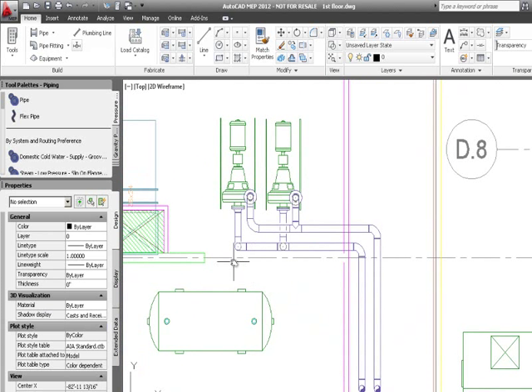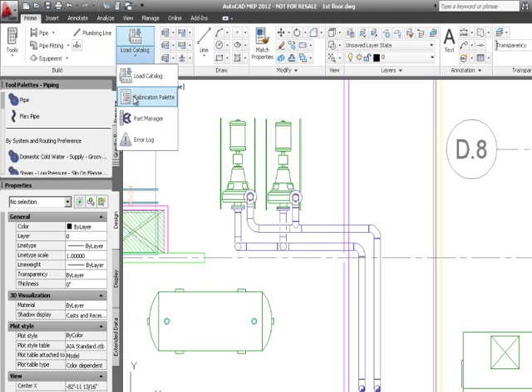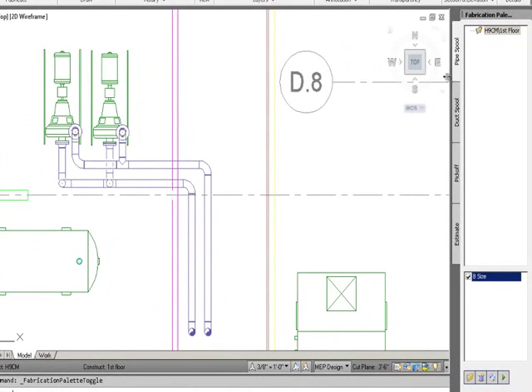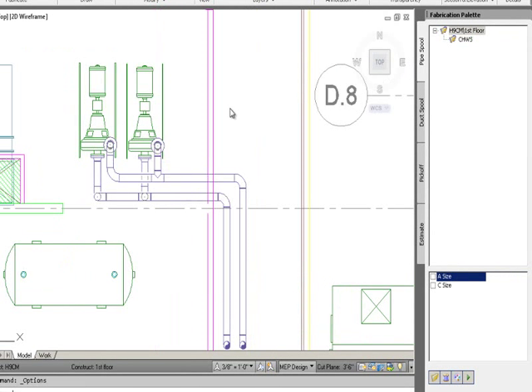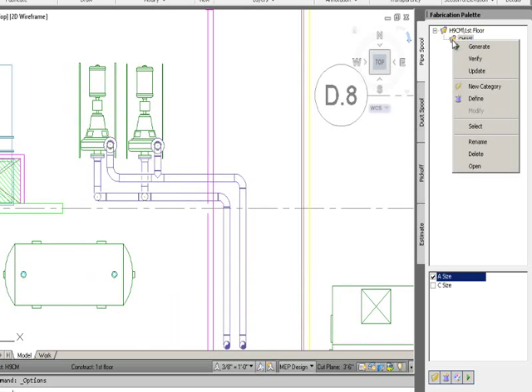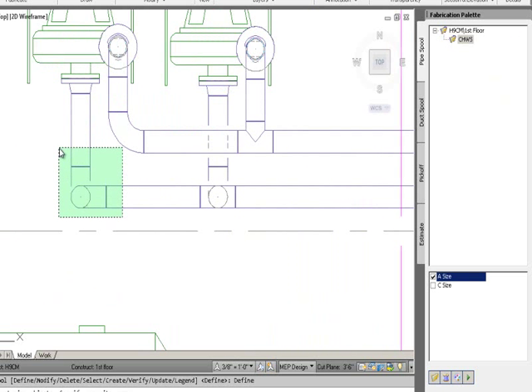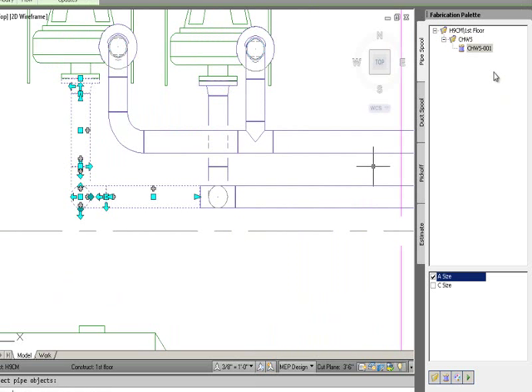Now let's start fabrication by creating some spools. I open the fabrication palette, go to pipe spool, and add a new category — naming it 'Chill Water Supply.' With that category created, I define spools by right-clicking and selecting 'Define Spools,' then selecting the pipe objects. The first selection generates spool CHWS001. I define again for spool number two, including a flange in that spool.